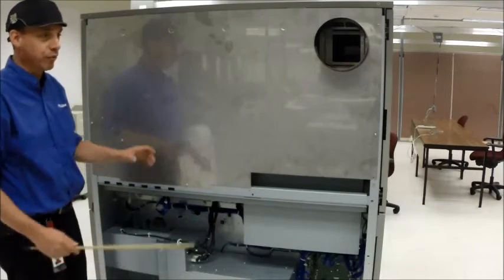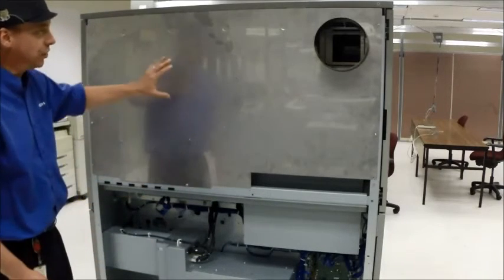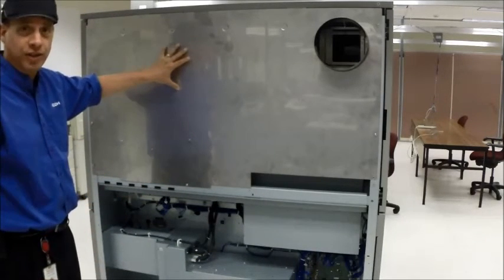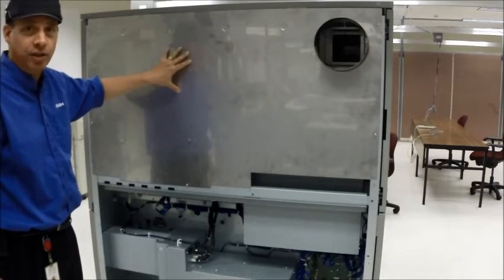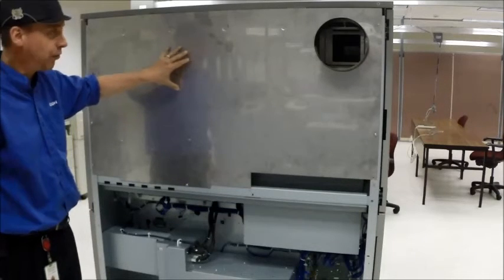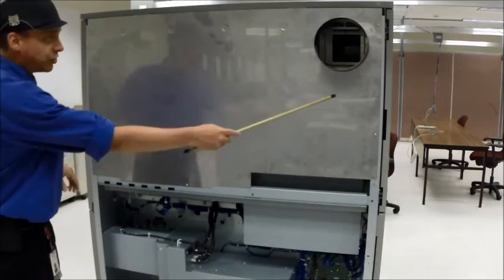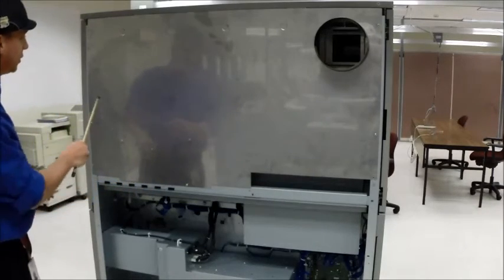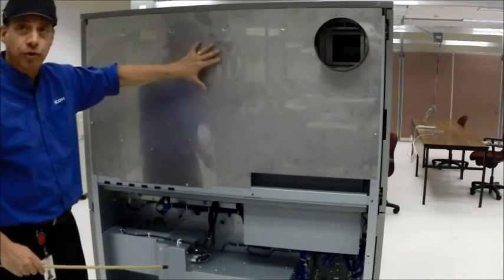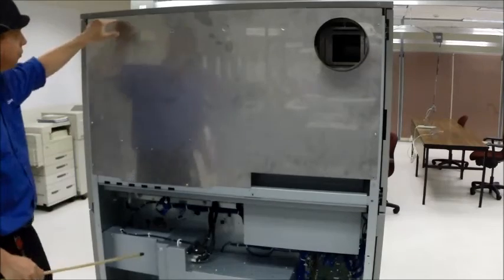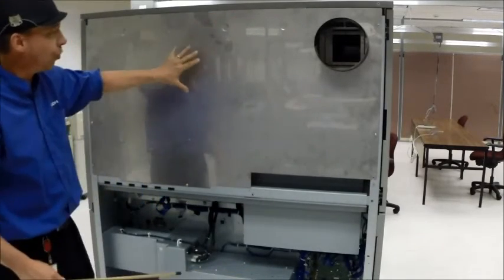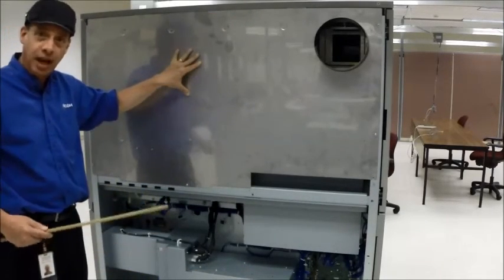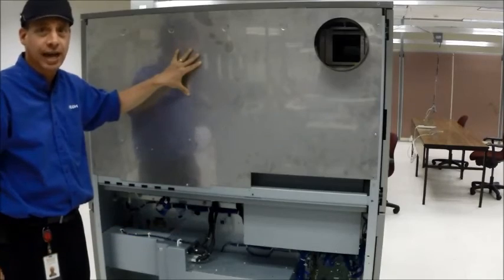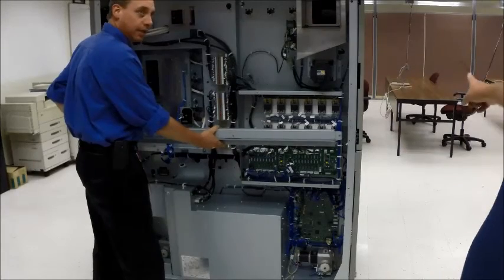On the back side, we've removed the outer covers, and you'll see a very large inner cover. This is stainless steel, and it's part of the condensation collection for the unit. There are a lot of screws here in the center holding the ductwork on, so when removing this cover, only remove the screws around the perimeter before lifting it off. Also be careful when lifting it, as it is very heavy.